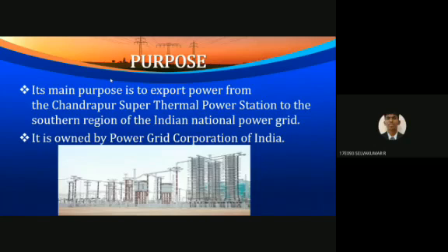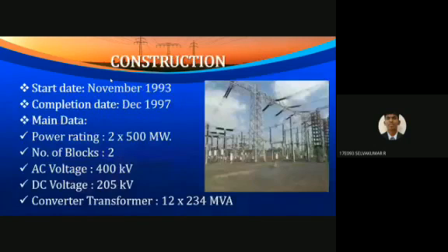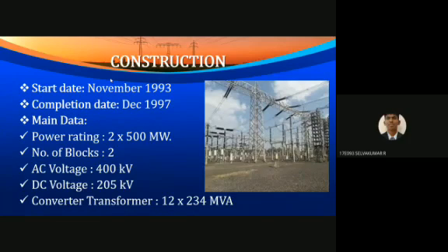It is owned by Power Grid Corporation of India. Construction-wise, this station also has two blocks, each carrying 500 megawatts. The AC voltage rating is 400 kV and the DC voltage rating is 205 kilovolt. The station has 12 converter transformers, each with a rating of 234 megavolt-ampere.